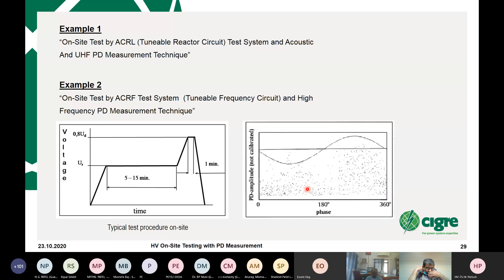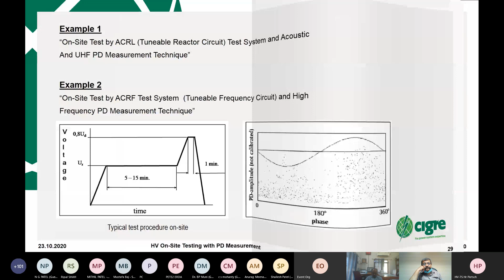A UHF sensor looks like that. I don't want to go into details. You have to get access to it. In some cases, it's already installed. In some cases, you can use windows, which are normally available at circuit breakers or earthing or switching compartments, and then you can pick up the signals from the outside through the window. And this is a typical way to proceed. There's a so-called preconditioning test, which is not clearly defined, and then you make the withstand test for 1 minute, and then you make the PD pattern. Again, with phase correlation, each single pulse is 1 PD. In that case, it was identified as a moving particle, which was found in one part of this compartment.